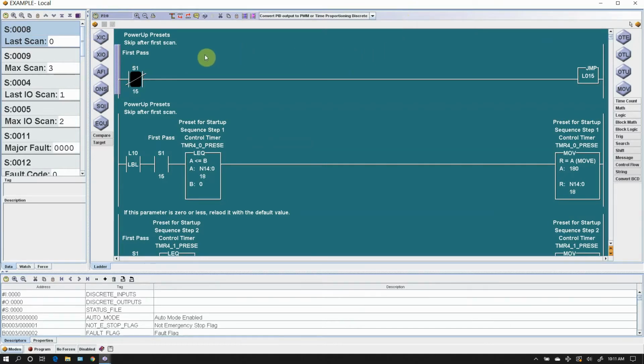So every icon has hotkeys for those of you that like keyboards. So here, if I hold this, the tooltip says it's Alt-N. If I hold it here, you'll see it's also Alt-N. So when I press Alt-N, wherever the keyboard focus is, that editor is what the keystroke will have effect on. Also want to mention while I'm up here, the rung number that the cursor is on is displayed here. This is the cursor. You can see now I'm on P2/1, which is program file 2, rung number 1.